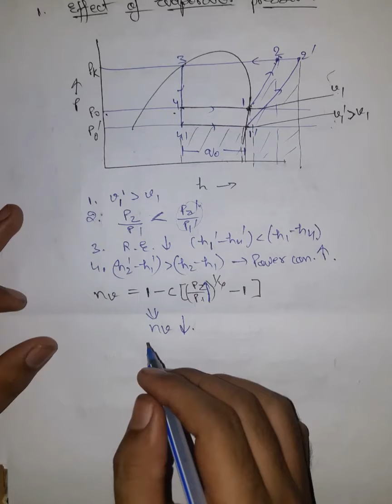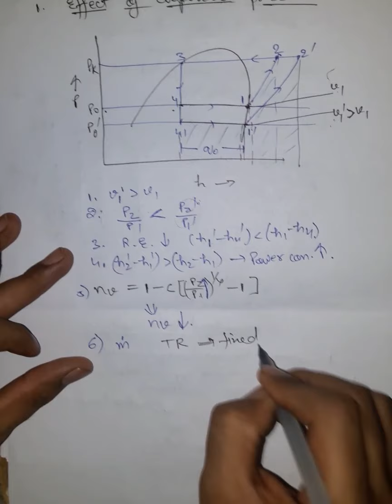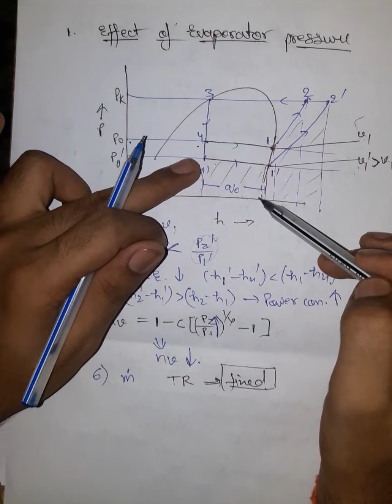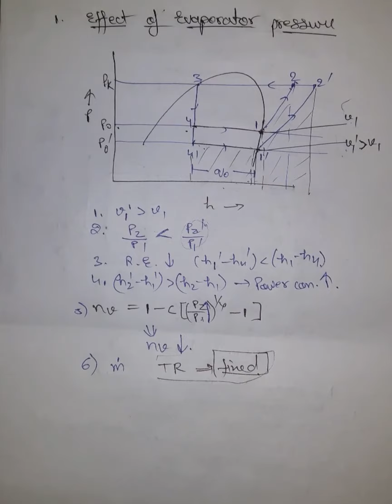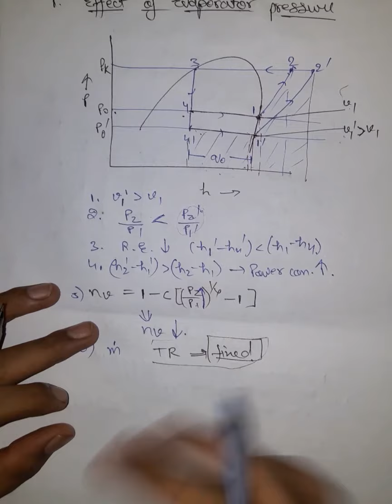Now we talk about the mass flow rate of the refrigerant. Would we need a larger or a lesser mass flow rate? Let us say the cooling capacity is fixed, that means the tons of refrigeration are fixed. For a fixed cooling capacity, we can see from the diagram that the refrigerating effect has decreased. A decrease in the refrigerating effect means we need to flow more refrigerant, because the tons of refrigeration are fixed. Let us say we require 10 tons of refrigeration. Earlier the refrigerating effect was larger, so a lesser amount of refrigerant was needed, but now the refrigerating effect per kilogram of mass has reduced, so we need to pass more refrigerant. So the mass flow rate increases for a given refrigeration capacity.